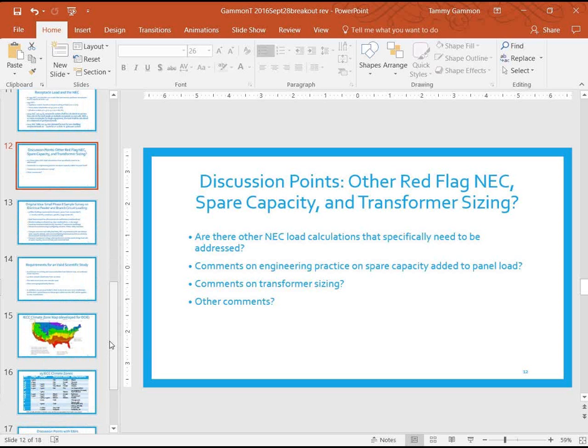Okay. There are some examples in hospitals. You know, when we went down this road, we understand that we're always getting the high voltage guys saying it looks like we're going to max out on forced air rating on a double-ended substation over the hospital. There are a significant number of installations that are running out of power at the service. It seems odd what's going on downstream, however. So that's at least at the utility interconnect where I did a fair amount of my career. There was always a problem certain hours, maybe at most 76 hours per year, where there was a problem at the service, and we were in danger of going into the forced air rating. And then of course you've got a rating beyond that, which is somebody with a hose, depending on the kind of transformer you have. If you have an oil filled, so a lot of it, the type of transformers are very subtle devices, believe it or not. Go ahead.